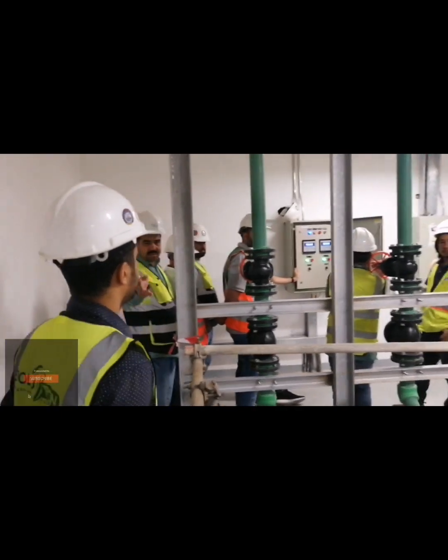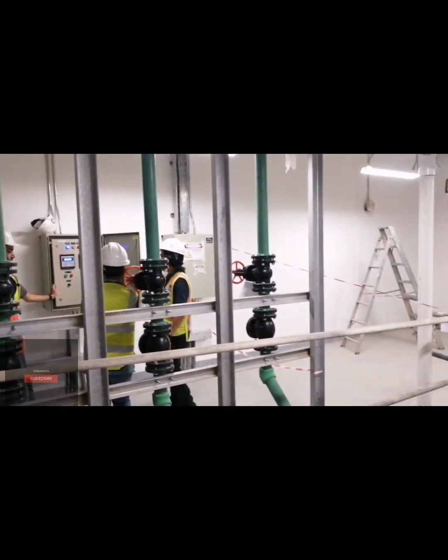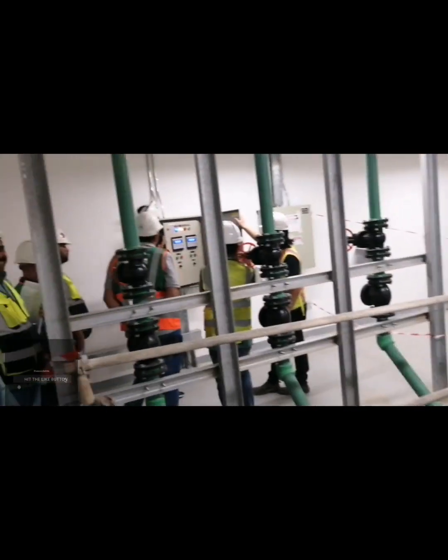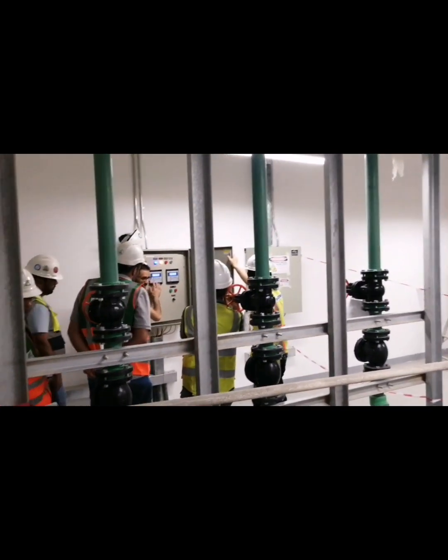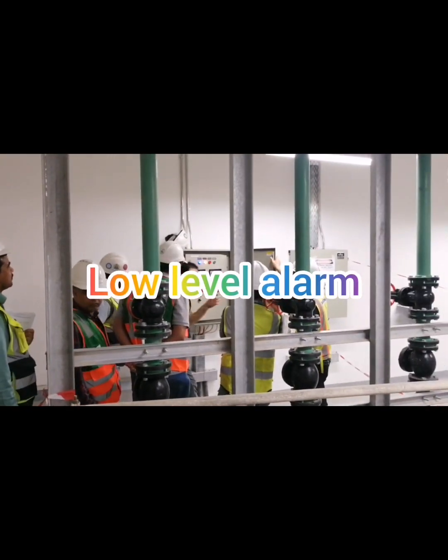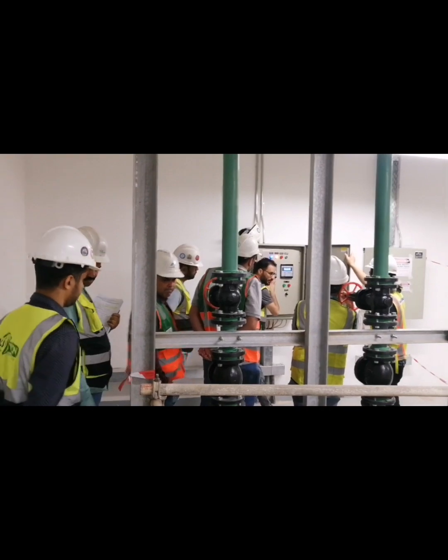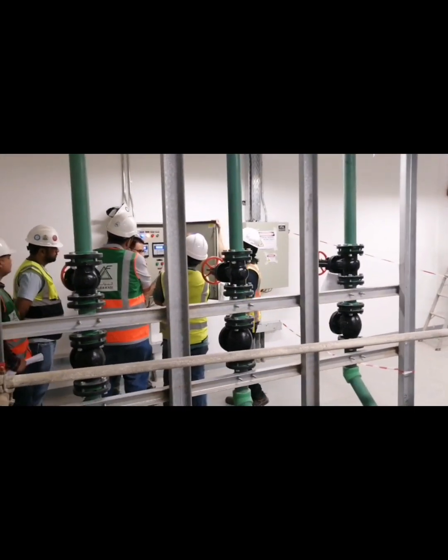The high alarm means both pumps are working, or it gives you an indication that the pump is stuck, or the pump has tripped, or there is something inside the pump — meaning there is an issue. It gives you the alarm to show you that something is happening with the pump.